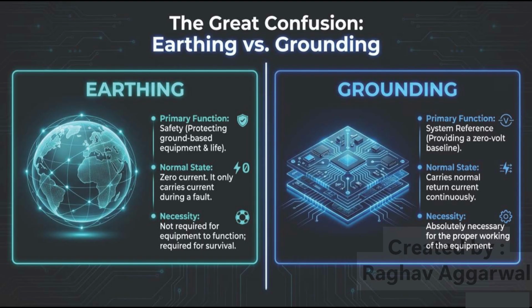One of the most common sources of confusion in industry is the difference between earthing and grounding. Although the terms are sometimes used interchangeably, let's highlight the important differences. Earthing is primarily a safety function. Its purpose is to protect people and equipment by directing fault energy safely into the earth. Under normal conditions, the earthing conductor carries no current. It becomes active only when a fault occurs.